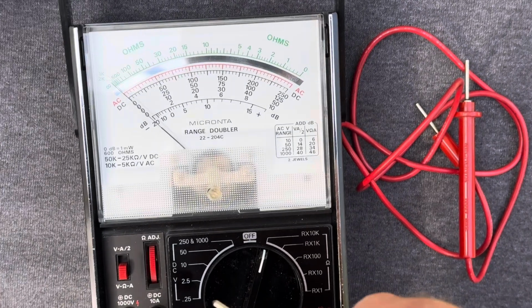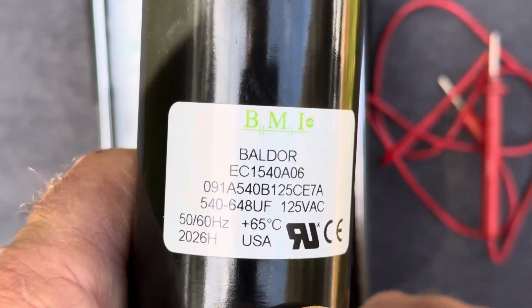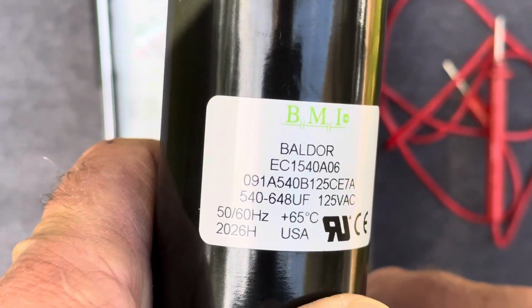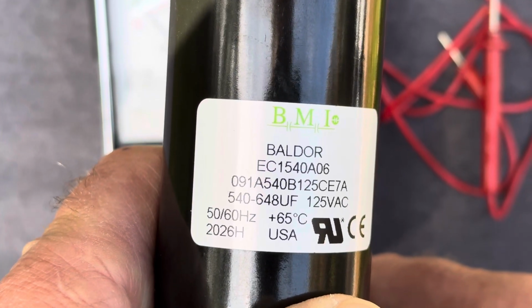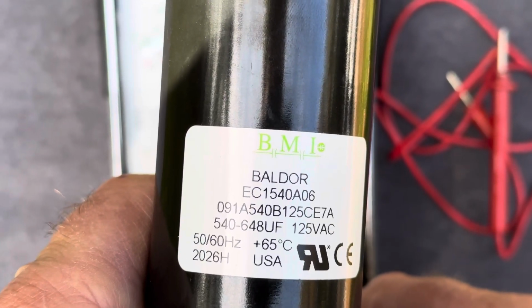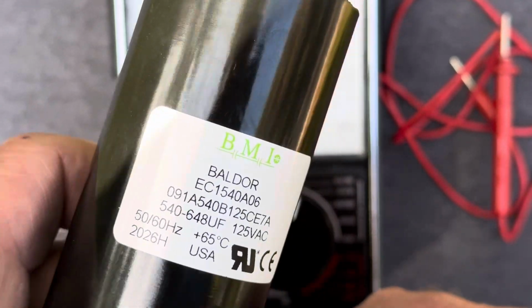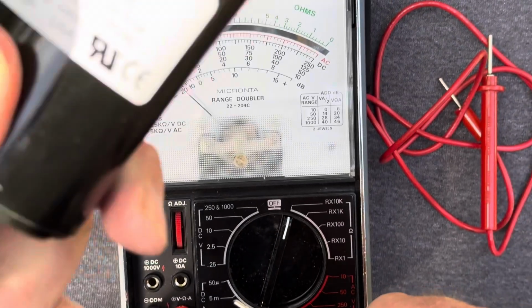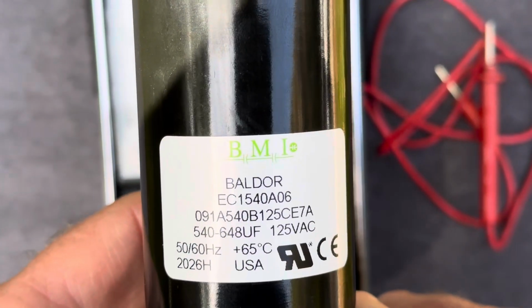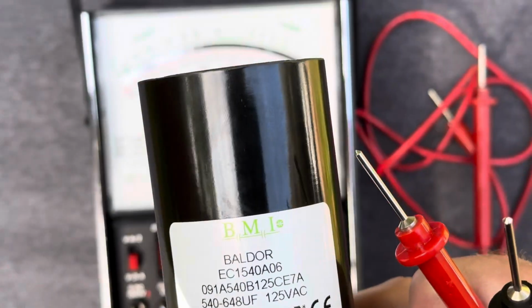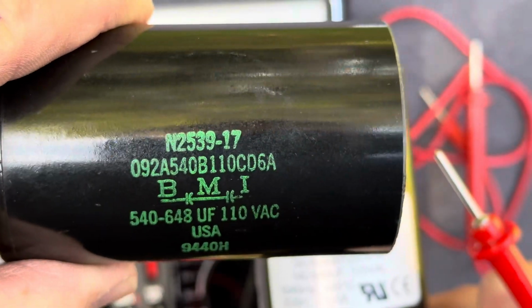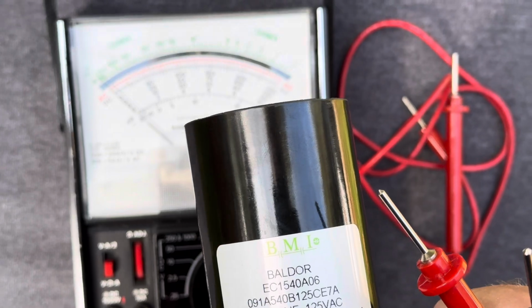Here's the new one, same rating, 540 to 648 microfarads, but 125 volts - a little higher voltage rating, but basically the same capacitor, same manufacturer, BMI. You see that on this one here too, BMI. I think that's Baldor motor.